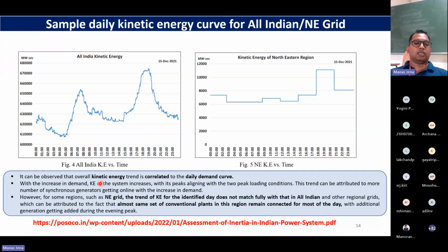So it can be observed that the overall kinetic energy trend is correlated to the daily demand curve. With the increase in demand, kinetic energy of the system increases, with its peak aligning with the two peaks, peak loading conditions, as I said, morning peak and the evening peak. This trend can be attributed to more synchronous generators getting online with this demand. With the demand going up, perhaps during that time more synchronous machines are coming into the picture.